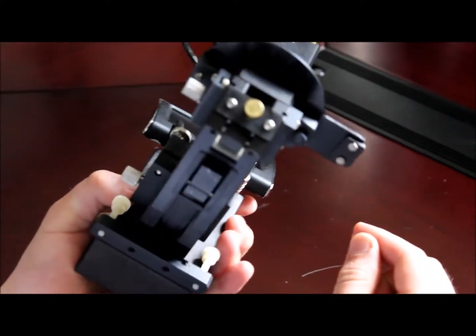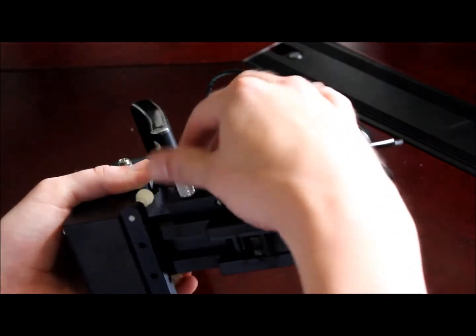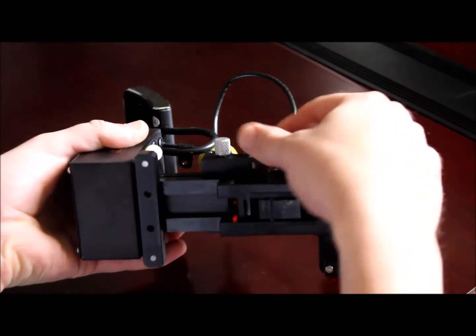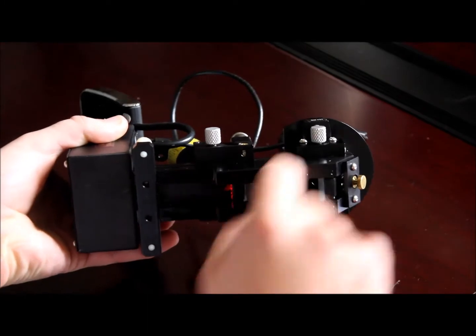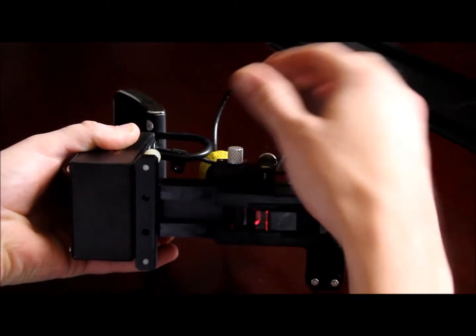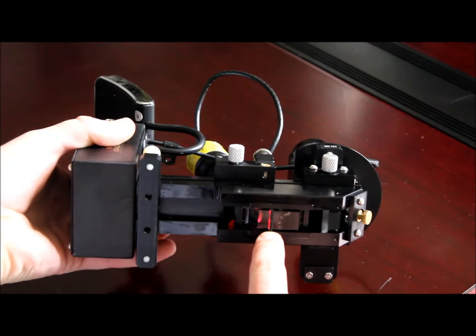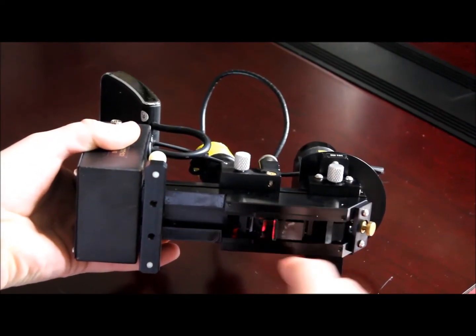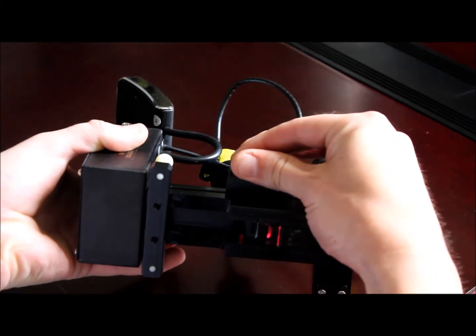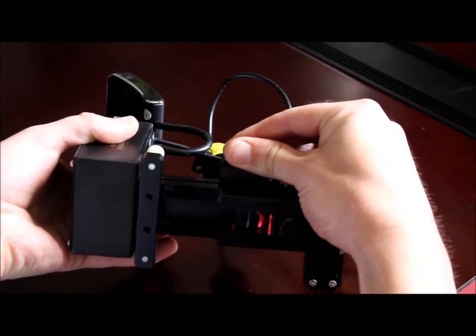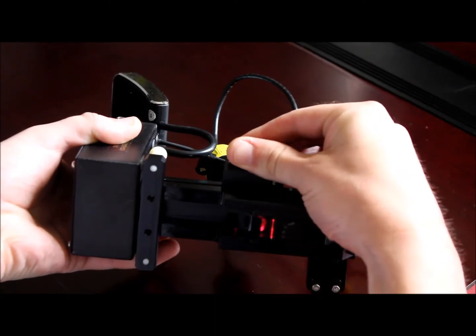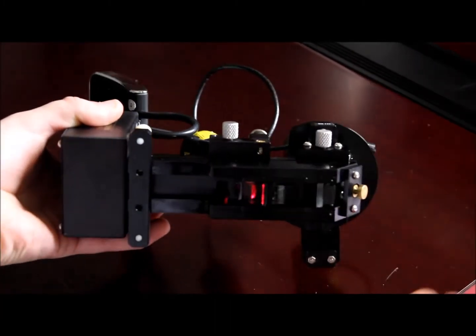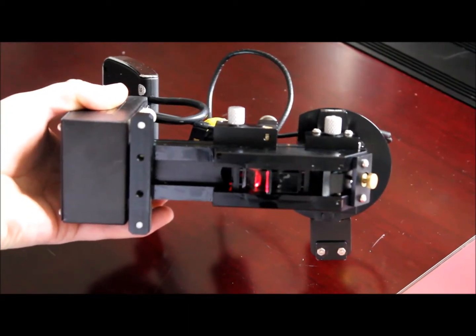The second step will be to actually turn on the instrument, and we want to be able to move the laser so that when we place it above this entrance prism, it's bouncing off of this reflective surface in a way that it creates as light a laser intensity as possible at this junction where the divider between the prisms is. So as I move that around you can see the light gets darker and brighter, we want it as bright as possible, and then we're going to lock that down. That should get us into a ballpark for once we decide to start measuring.